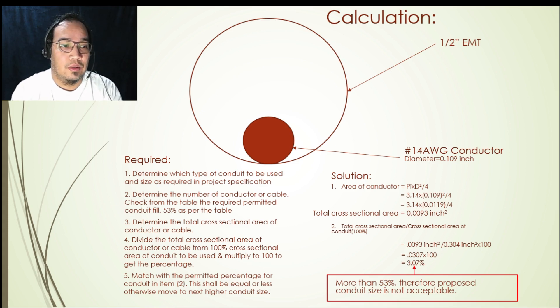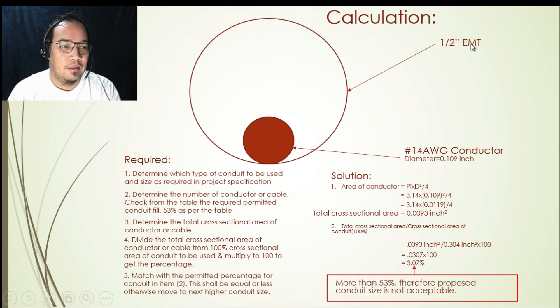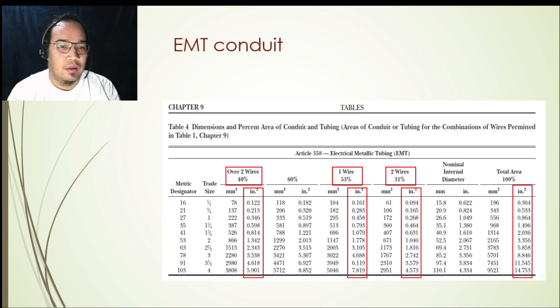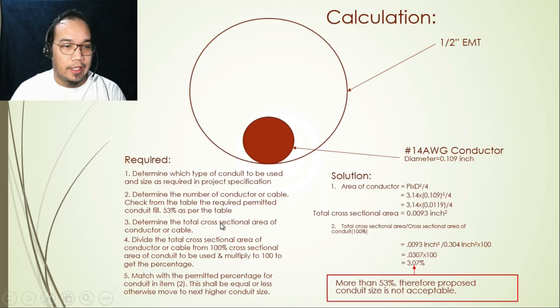For the sample calculation, the first step is to determine which type and size of conduit to use. In this example, we are using EMT, 1/2 inch size. The second step is to determine the number of conductors or cables inside the conduit. In this example there is only one conductor, so referring to the table, we can only use 53% of the total cross-sectional area of the conduit.